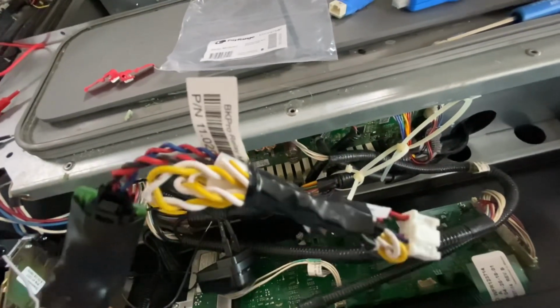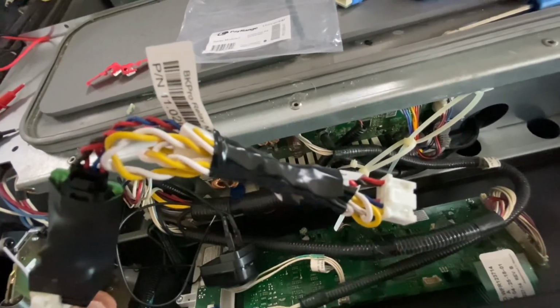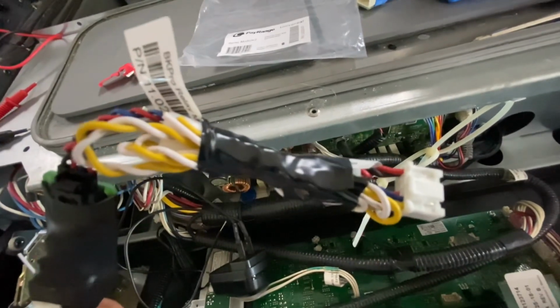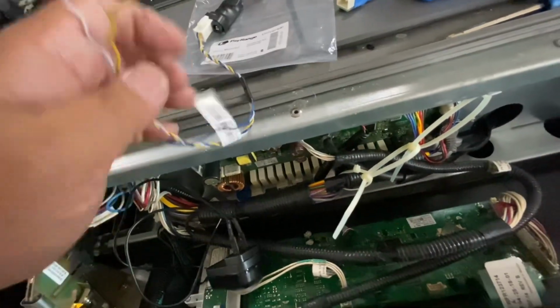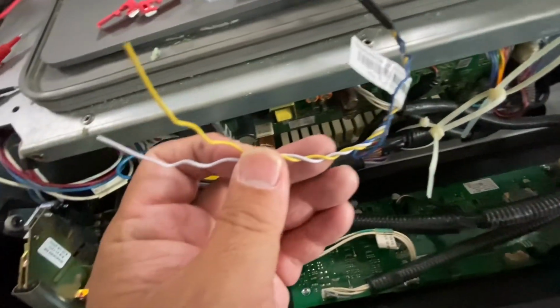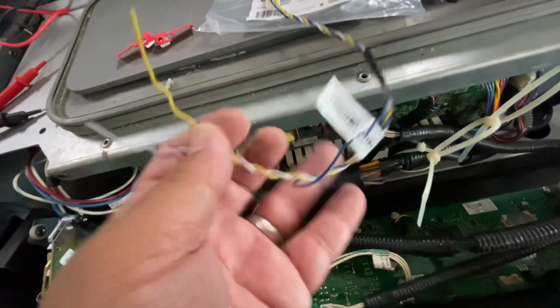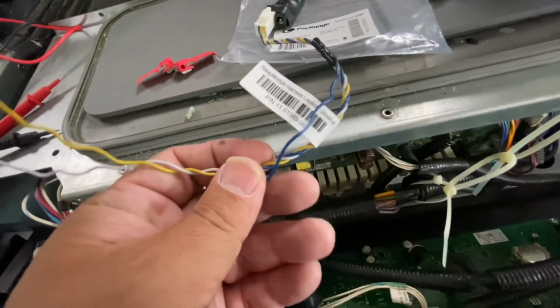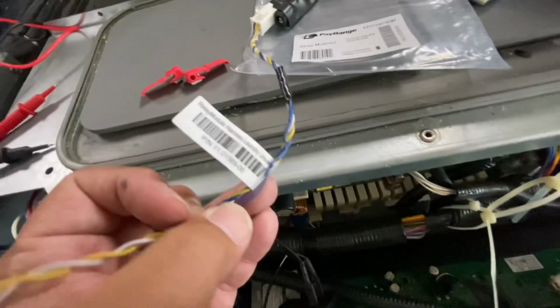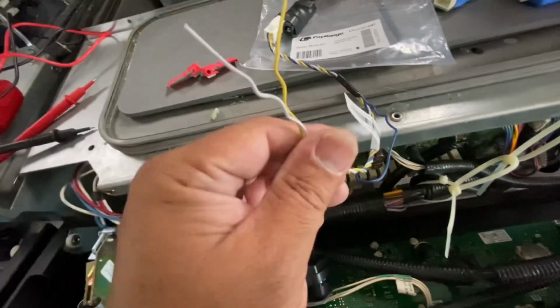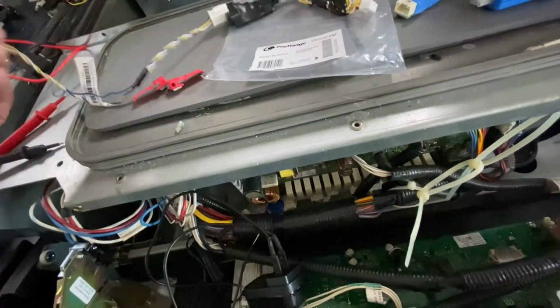On your relay kit, there are two ends. This end has a yellow and white wire, which you will not need, so just bundle it up and tape it out of the way with some electrical tape. The other end has three wires: yellow, white, and blue. In the case of Maytag, the blue wire isn't used, so tape it up and get it out of the way, and separate the yellow and white wire before that.